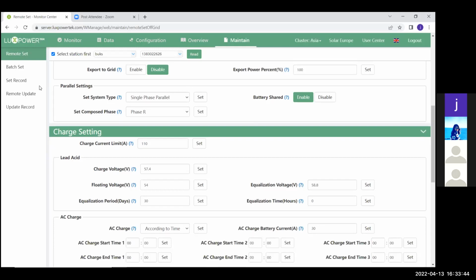Now, parallel settings are quite easy on these machines. You can put it on single phase parallel, like this guy has 2 units, so that's why it's on single phase parallel. There you can also go to 3-phase parallel. There's no master setting or anything on these inverters. The first inverter that you switch on is the master in the string. So you switch on the first inverter, then the second one. The first one will be the master.